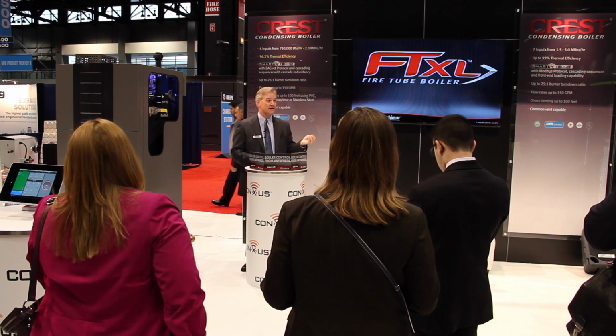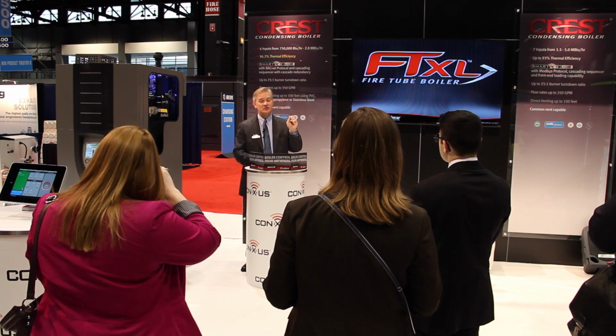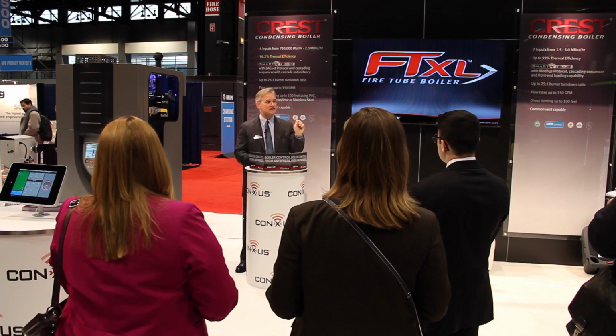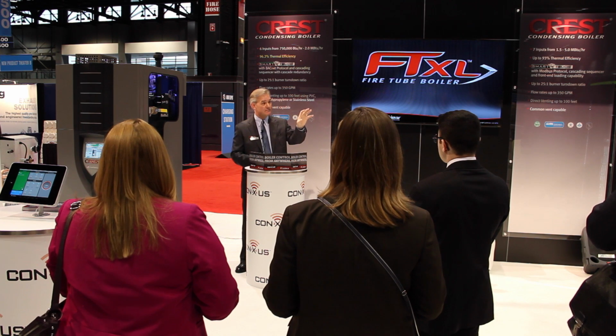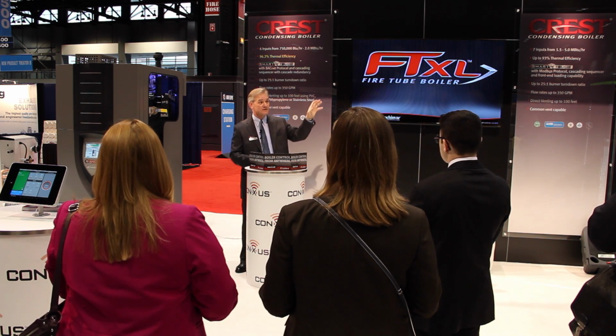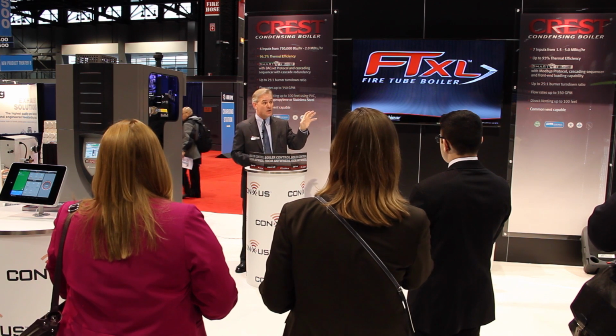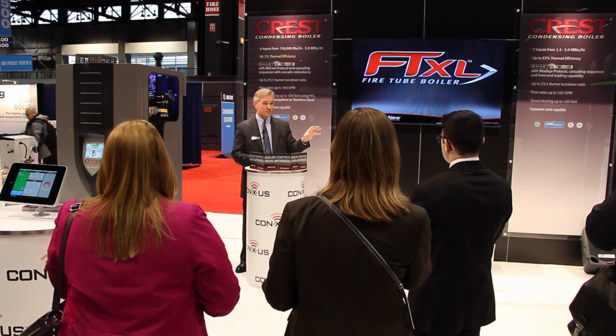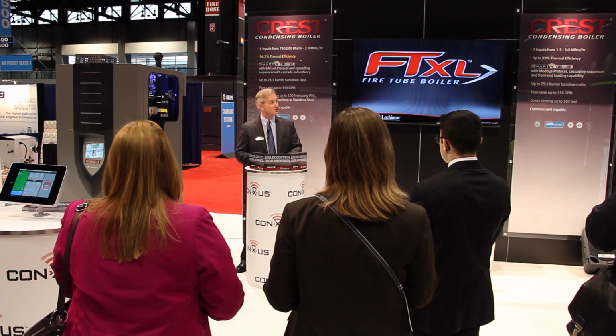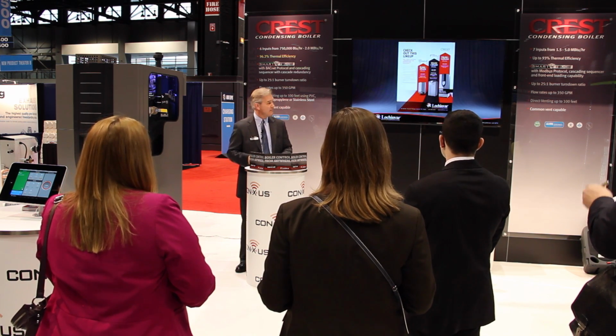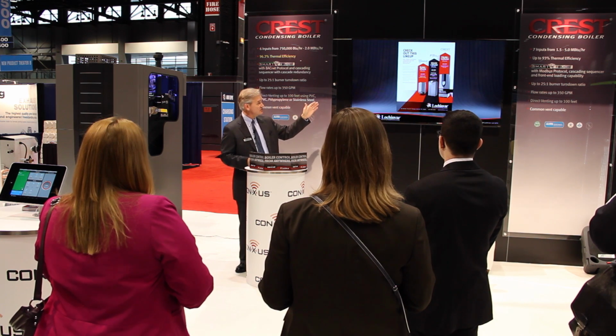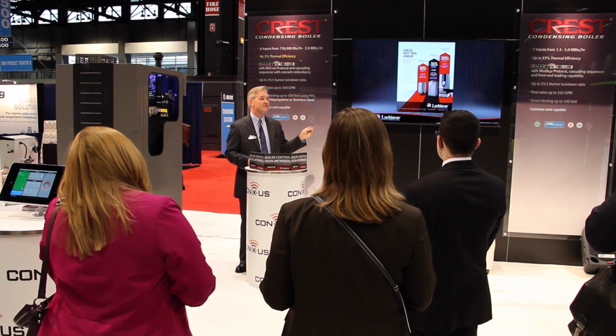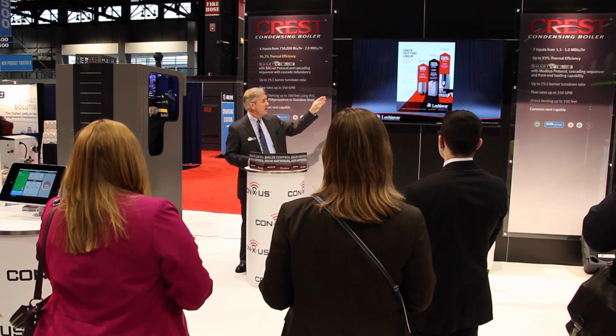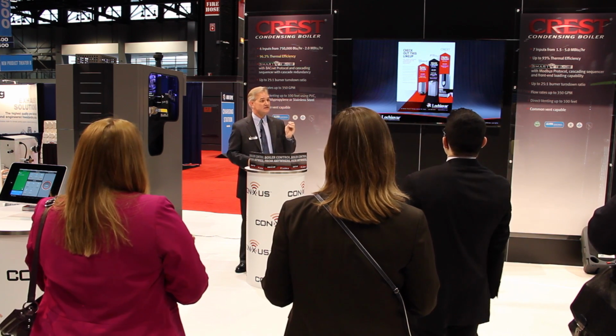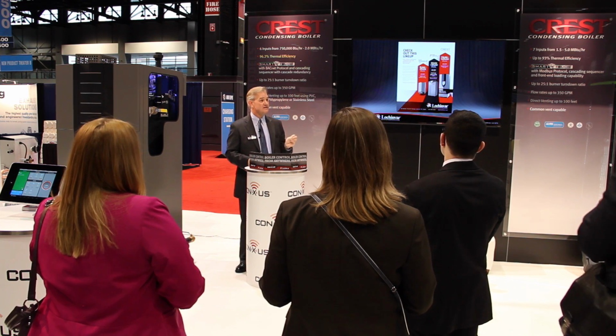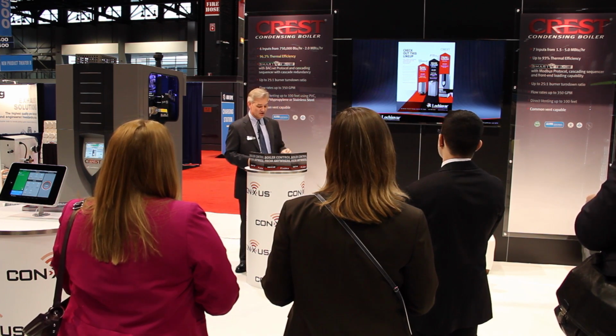Its high efficiency at 98% reduces operating costs, and it features a 0 to 10 volt DC variable system pump input so that a system pump can be harmonized with the boiler's control, so as the system demand changes, the boiler's firing rate changes. We're now talking very good system efficiency with the product, and it's the first of its kind in the industry. I'd like to show you this. Check out this lineup. In the last 4 years, Lochinvar has transcended with a fire tube condensing line from 55,000 BTUs with our WHN all the way up now to 5 million BTUs in stainless steel, high efficiency condensing boilers. That is a lineup that really is unmatched in the industry.